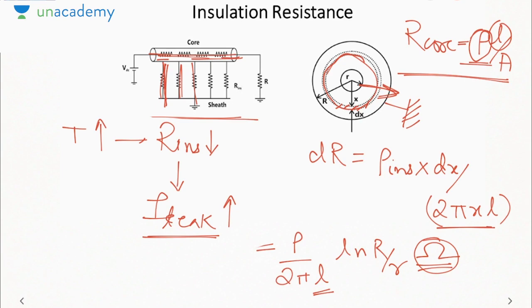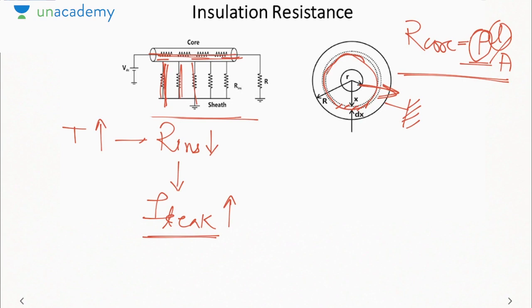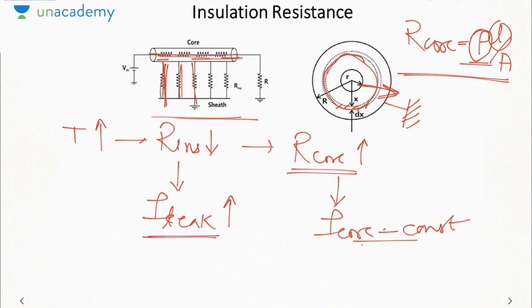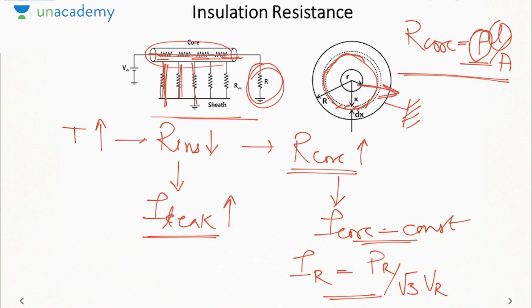And what about the core? Conductors have a positive temperature coefficient. So as temperature increases, core resistance will increase, so R core will increase. So what will happen to the conductor current or the core current? I core is constant. Why? Because I core is determined by something like P by root 3 V cos phi. It does not depend on the resistance of the core, rather it depends on the load. So I core will depend on the load resistance but not on the resistance of the cable. Whatever the core resistance is, that does not determine the current that flows through the core. So that is about the resistance of the insulating layer. Now as I told you, we choose the dielectric based on the maximum electric field inside the underground cable. So we have to estimate the electric field distribution and then determine the maximum electric field in the cable.